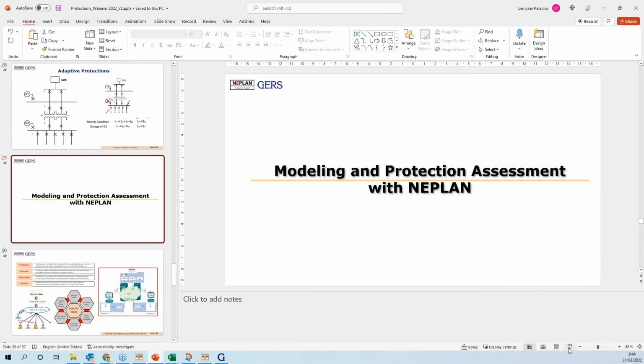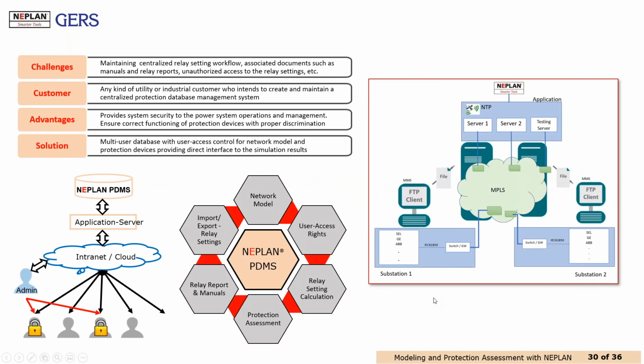Well, however, the NEPLAN web services have many advantages. For example, the protection device management systems implementation, because in this architecture, we can see how in real time we can import and export the relay settings. We can validate them on the network model. We can give permissions, level access for the users, and validate the relay setting calculation and check if for specific topologies they are working or not. So the architecture using NEPLAN web services allows to implement customized solutions for any kind of customer.